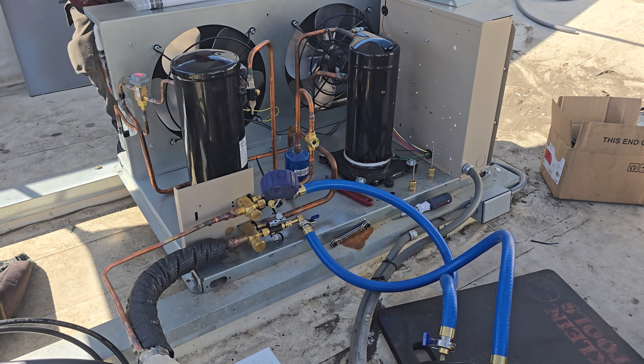The really cool thing about the Intelligen evaporators is that the EEV, the electronic expansion valve, comes in the mid-seated position. They're open, so we can flow nitrogen and evacuate. Once you turn on power, it closes, and then you have to wait for it to call for cooling for it to open again. So keep that in mind when working on these - don't energize until you're done with your vacuum.